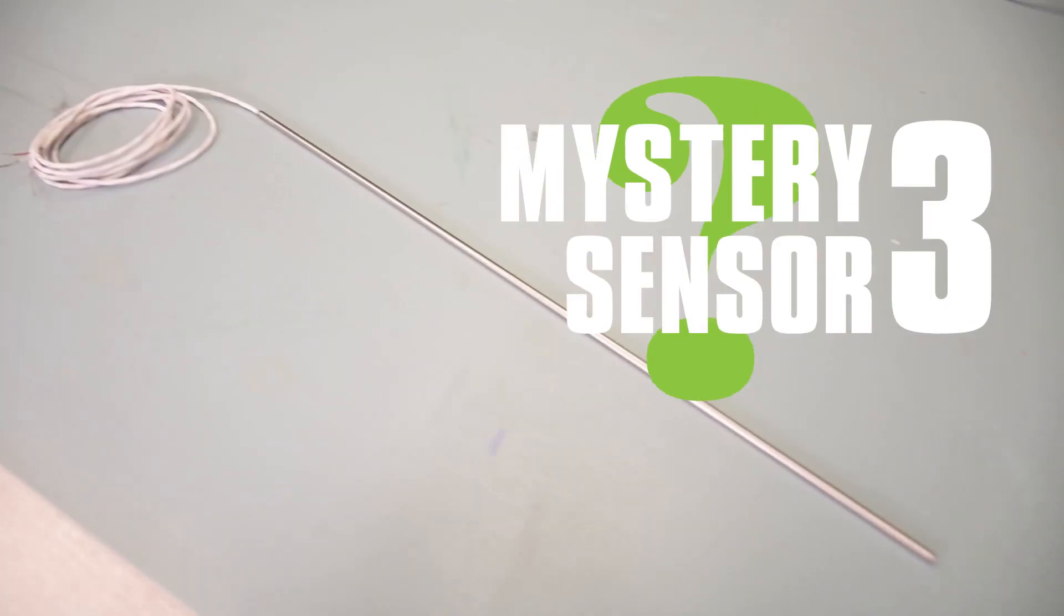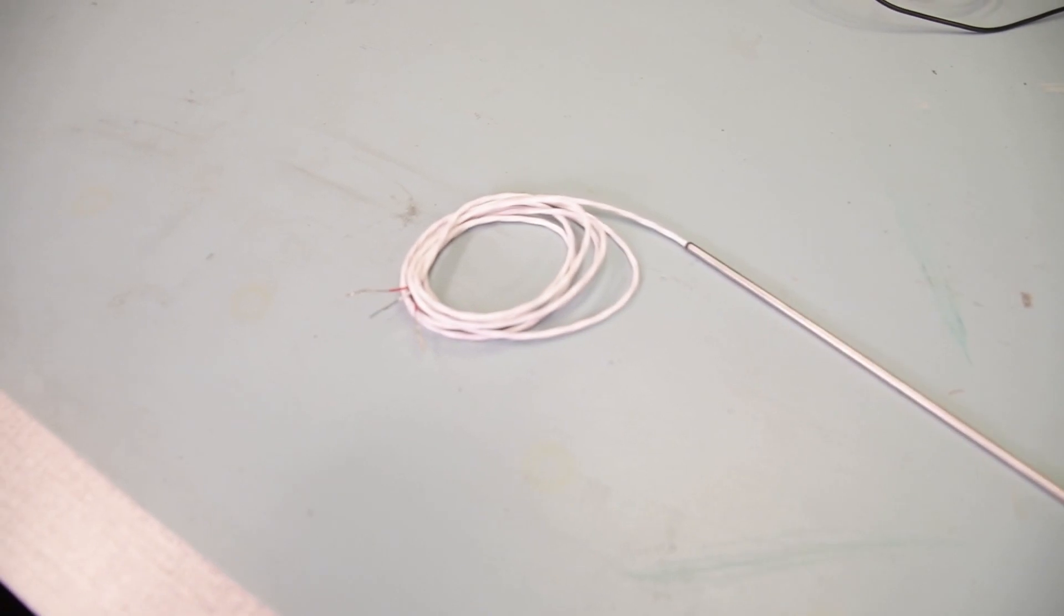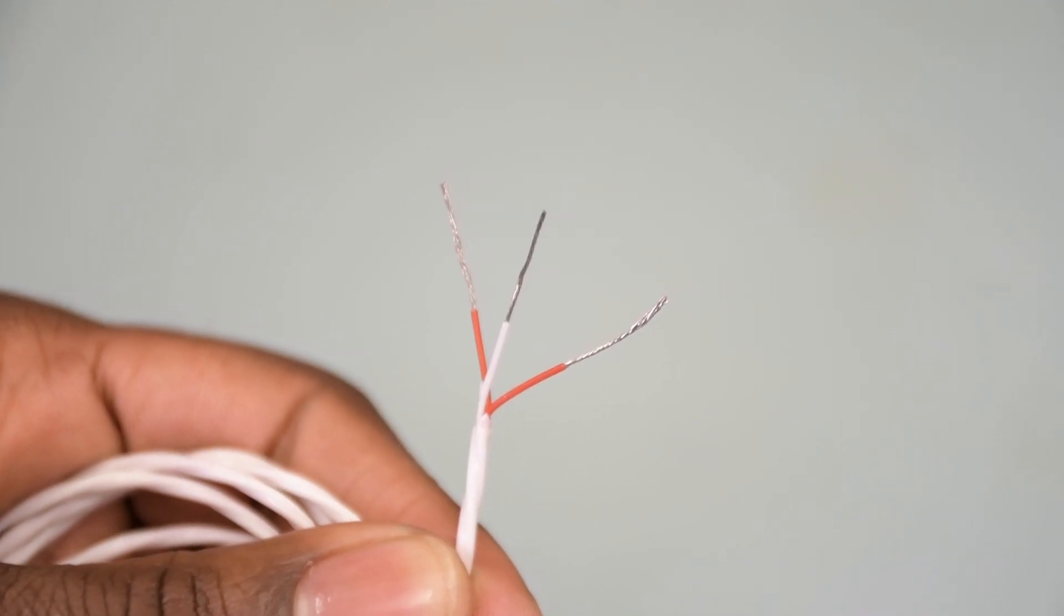Now, onto mystery sensor number three. This probe has a metallic sheath, no transition joint, but it does have a cable on the end, and has a three-wire construction.